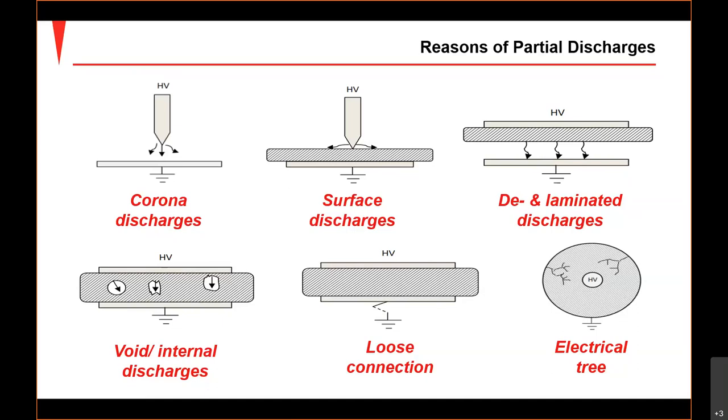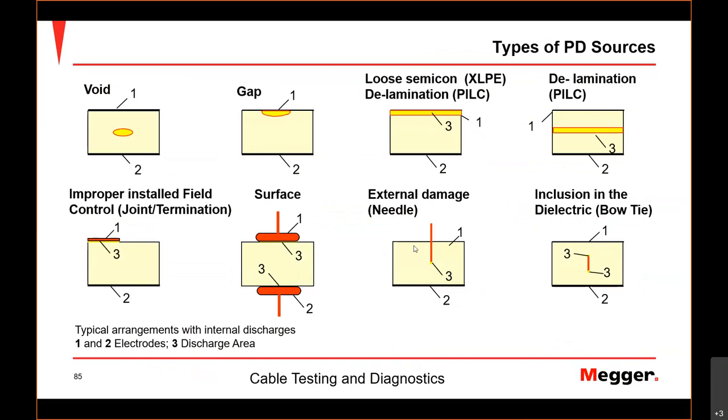Right. And here are some more examples. If you have a little metal chip there or an air bubble, this, for example, would be the example with this bad shrinking of a joint, right? Or here, this example would be the one that we saw on the photograph, where this mastic tape, this semiconductive tape, was missing. So the semiconductive layer was just peeled off and left just cut there. And then you get a very high electric field stress here in the corner, and you get arcing there. Like delamination, that's like when paper layers run dry on the paper cable, for example, right?